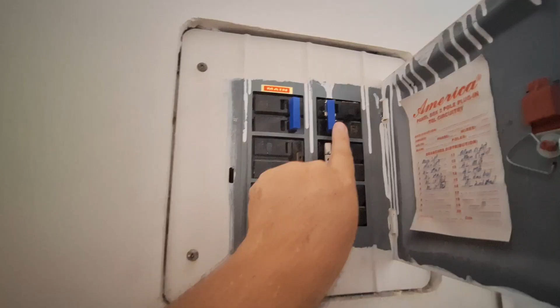You can see that this breaker is on, to the left, which means we're using the hybrid inverter, hooked to the grid. Remember, we've been running like 195 to 208. They made the tap adjustment, and now it's right at 230, so it looks like it fixed it. We've been running 230, 231 with solar, and now we're running 230, 231 back on the grid. So everything has equalized and we're back to normal.